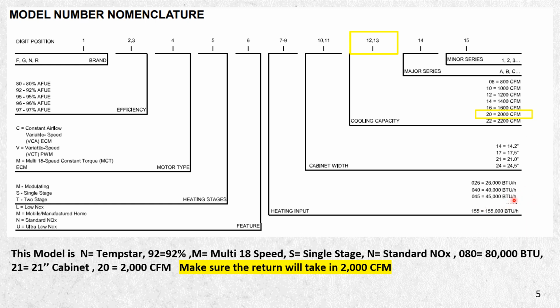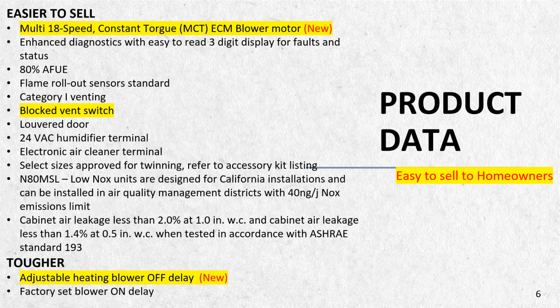So make sure when you're using this particular furnace that you're using a like a 5-ton setting, or that you got to have 80,000 BTU. Now you also want to keep in mind too that 80,000 is on the low end of a 5-ton, so you could actually use this one for a 4-ton or 4.5 in that range. If you need a little bit more than 4-ton, you'll have a 5-ton drive, a 2,000 CFM capability, and you can also slow it down, and we'll show you how to do that in this video as well.